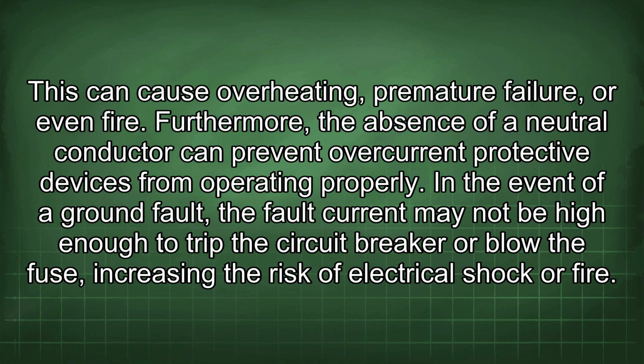Furthermore, the absence of a neutral conductor can prevent overcurrent protective devices from operating properly. In the event of a ground fault, the fault current may not be high enough to trip the circuit breaker or blow the fuse, increasing the risk of electrical shock or fire.